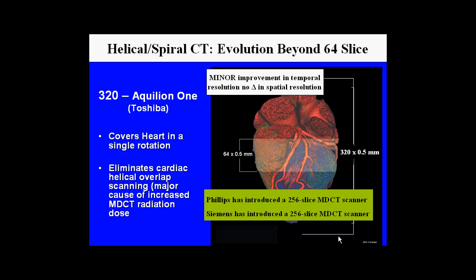Toshiba has recently introduced the 320-slice scanner, which provides entire coverage of the heart in a single rotation. This is very important because it eliminates cardiac-helical overlap, which is a major cause of increased radiation dose for multi-detector CT scanning. Philips has also introduced a 256-slice scanner, and Siemens has introduced a 256-slice multi-detector scanner.